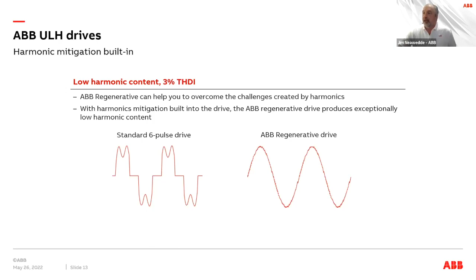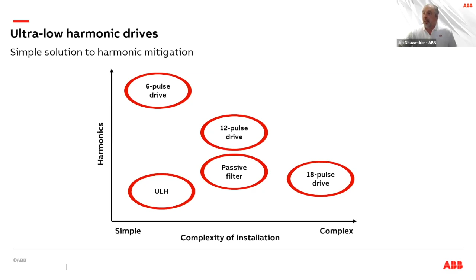So there are a lot of challenges associated with devices that create harmonics. Now, there are a lot of ways you can correct those harmonics. Some of those are fairly simple, and some are more complex. The level of harmonics produced is shown here on the left axis. Your biggest contributors to harmonics would be your 6-pulse and 12-pulse drives. You can put passive filters on those. You can go to an 18-pulse drive, which has a reduction of harmonics, but it does have complexity. It requires a lot of extra devices, and passive filters require extra wiring and installation costs. So the ULH solution is probably the easiest to install and has probably the lowest cost overall.